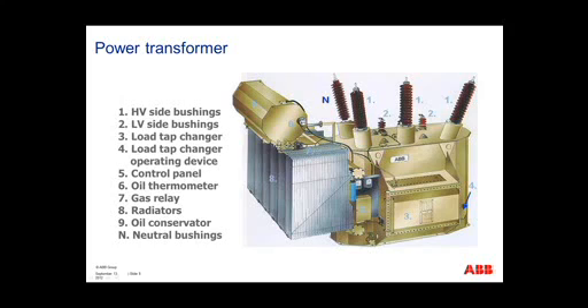Numbers 1 and 2, other important aspects, are the bushings. This is going to be your connections to the high side of the transformer. Your high side voltage would be 1, and similarly 2 would be your low side bushings, considerably smaller than high side bushings. And of course, this is dictated by what type of voltage you're connected to.